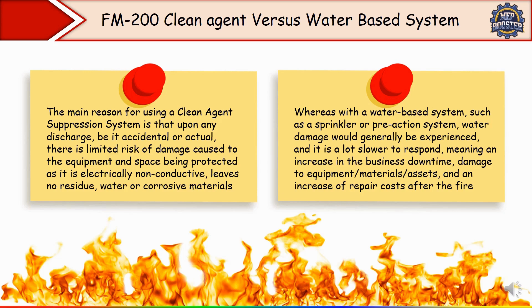FM-200 uses heptafluoropropane, a gaseous fire suppression agent — colorless, odorless, and non-conductive — while a water-based system uses water or foam as the extinguishing agent. FM-200 is best suited for areas where the presence of water could damage equipment, data, or critical assets, making it ideal for data centers, telecommunication rooms, libraries, museums, UPS rooms, and switch rooms. It is also suitable for areas where humans are present, as it is safe to discharge in occupied spaces. Water-based systems are commonly used in general building protection where water damage is not a concern — warehouses, manufacturing facilities, residential and commercial buildings, and parking garages — and in high-hazard industrial areas where large quantities of water are needed to control fire.